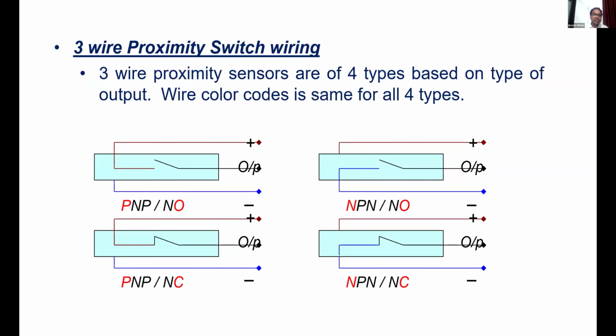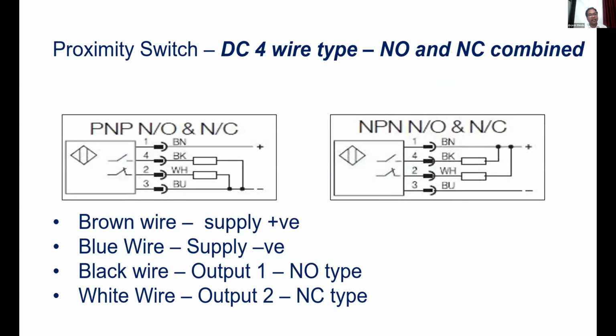Now see here, again the sensor is connected in 4 types. There are mainly PNP-NO, PNP-NC, NPN-NO, NPN-NC. And how we have divided this type is where exactly we will connect the output. For example, once the sensor senses there is no moisture in the agriculture land, at that time the pump will get automatically on. At that time, I will connect the motor's output to this output black wire part. And with the help of this diagram, we can see how exactly we can connect the wire.